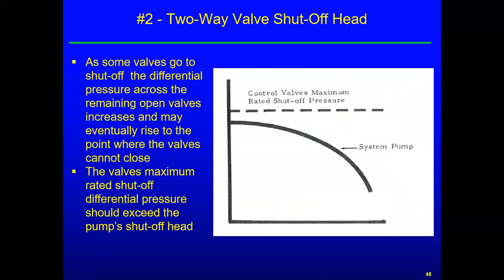Okay, another issue that comes up with these two-way control valves would be, are they strong enough to shut off against the pump head? And that's a good question, because if not, then as some of the neighboring valves start closing off, it's going to drive up system pressure. And if the valves aren't strong enough to shut, then you're going to be forcing hot water, say if this is a heating situation, through a valve that's trying to close, but it's not strong enough. And so that would cause major problems in the operation of the system. So you've got to make sure that the valves are strong enough to close off against more than the maximum pressure that the pump could ever deliver to them, so that you maintain controllability.